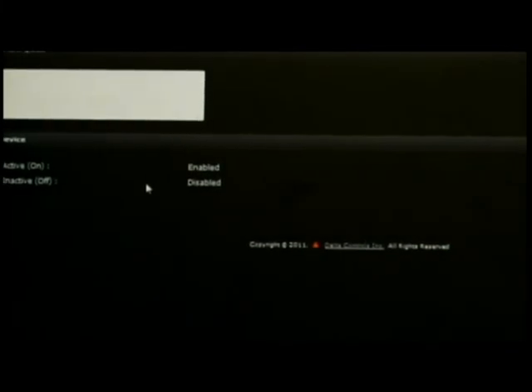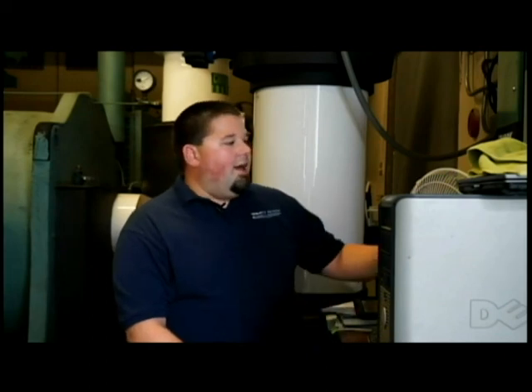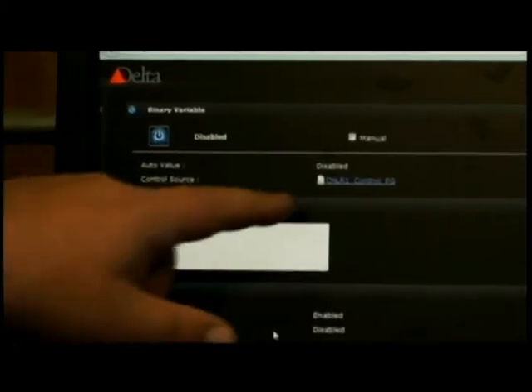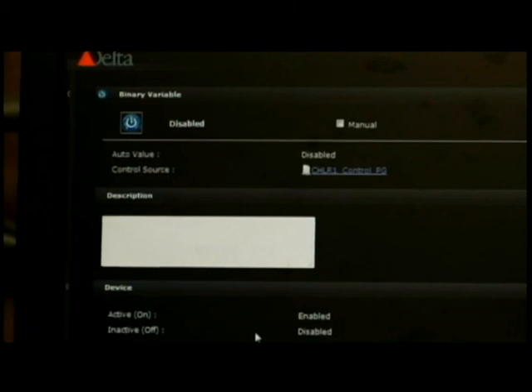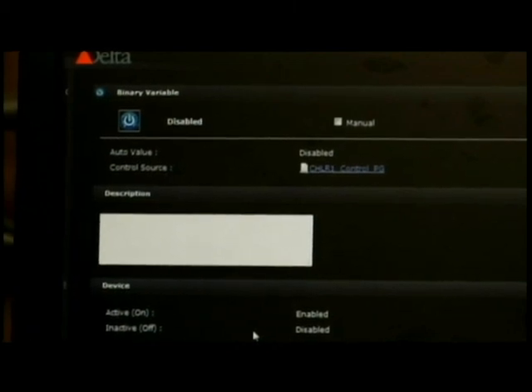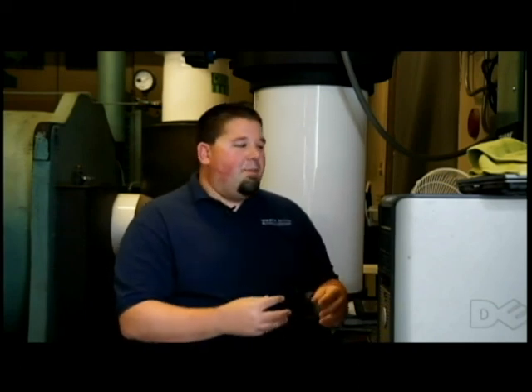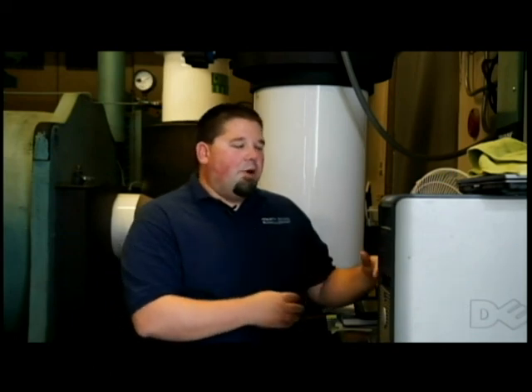But if you open up that point, you come inside here, we can see it's in auto control because the manual box is not checked. And our auto value is disabled. So that means when we're in auto, this is what our value is gonna be. And its control source tells us the page of programming inside the controller that is saying, hey, this should not be enabled right now. So you can use that as a tool to start troubleshooting as you get more in depth into the GCL programming and coding language in here to start troubleshooting issues with the controls.